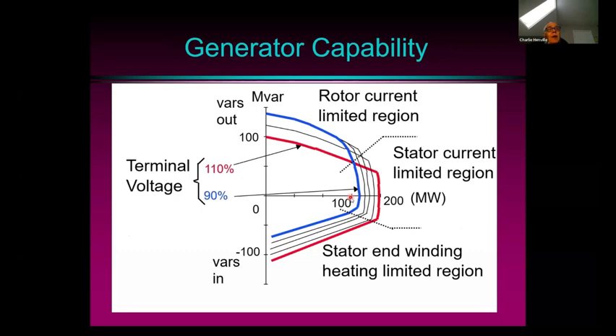Generators, of course, are very handy for being able to boost the reactive power. So we see the capability diagram of an example generator here. As the voltage gets lower, the excitation system will try to boost the voltage, and we notice that it can deliver more reactive power. Along this axis is the reactive power output of the generator, and along this axis is the real power output. Normally operators like to operate in this region here, or even close to 1 per unit. But the generators are capable of boosting the reactive power delivered to the system, and thereby boosting the amount of real power that can be transmitted through your transmission system.